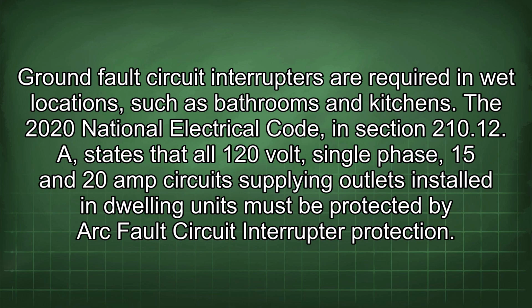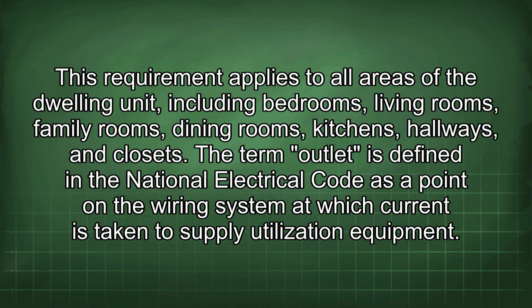The 2020 National Electrical Code, in Section 210.12(A), states that all 120-volt, single-phase, 15 and 20 amp circuits supplying outlets installed in dwelling units must be protected by arc fault circuit interrupter protection.